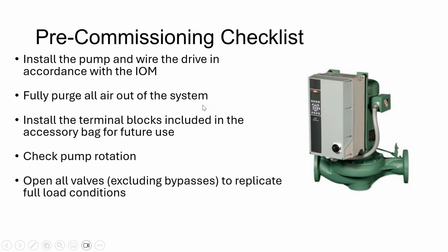If there's air in that system, it is going to cause problems for the pump slash drive once it starts to try to settle in and get started up. Install the terminal blocks included in an accessory bag for future use. So don't throw the bag away. You've got to take the box out and install them in the drive, right? You open this up and put them in. It's pretty straightforward. Check pump rotation.